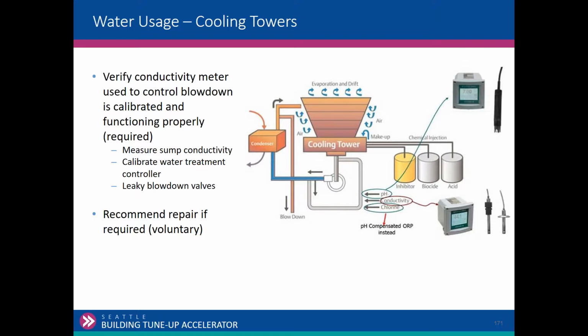Conductivity meters, I have one here in the library. They're around $200. A logging conductivity meter is a little bit more expensive. I don't have one of those, but I have a static measurement. So we can measure that, look at what the conductivity is reading, and then calibrate if required. So that's required for cooling towers. The other area that you can note is leaky blowdown valves, valves that remove water from the tower even though they're closed.